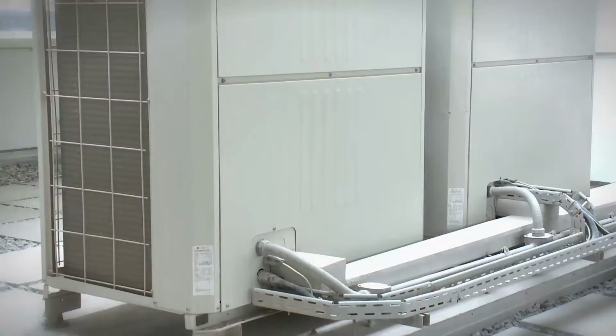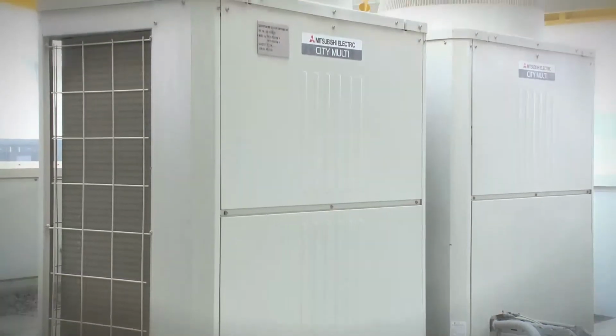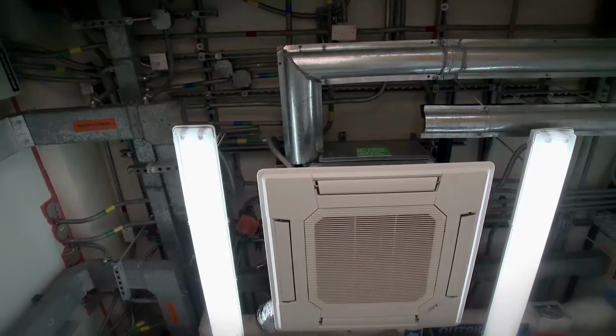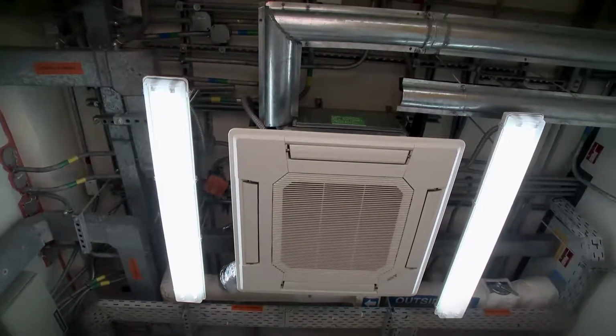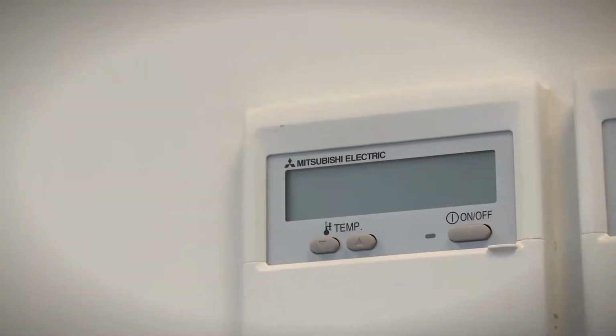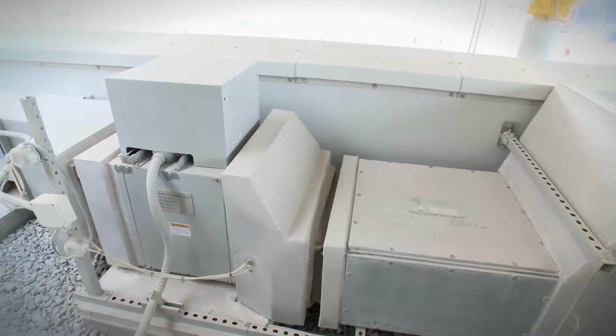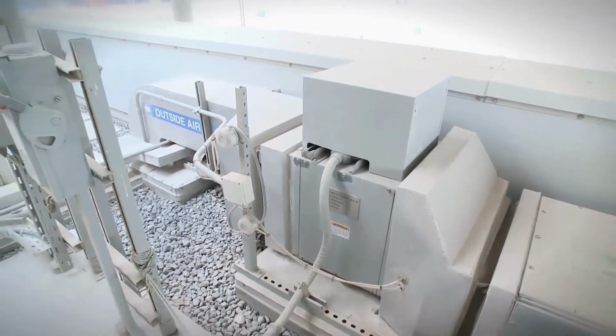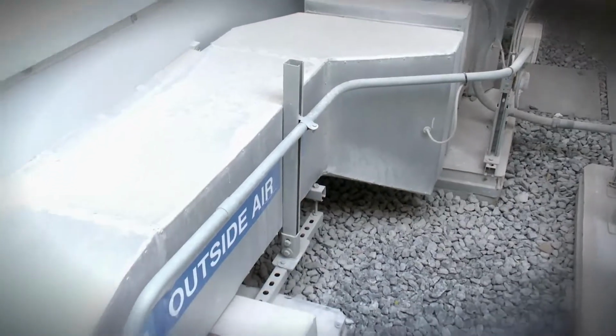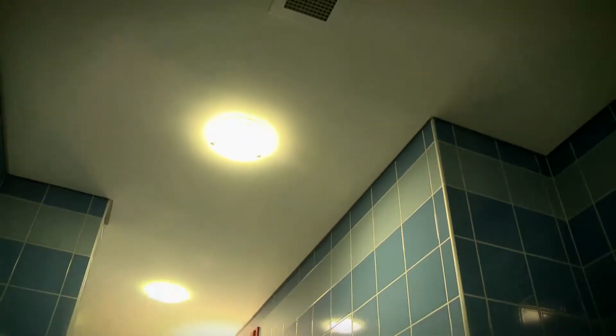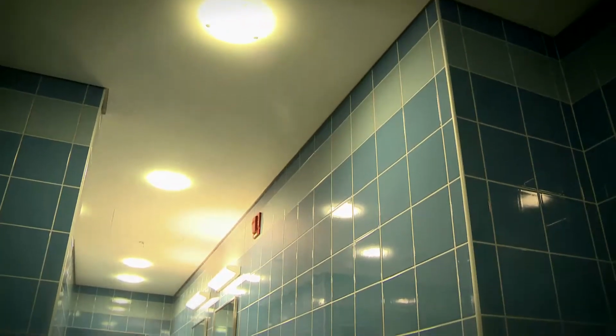The cooling requirement is 24 degrees centigrade, and relative humidity is 50 percent. In order to achieve this cooling requirement, we are using the variable refrigerant volume split units, which will be installed on the roof, and we have the cooling unit inside each room, and each room is controlled by its own thermostat. Whatever temperature you need, you can set it individually in the rooms, and then each unit is supplied with fresh air, so that you will have good quality of air inside the building. Simultaneously we are extracting the air from the kitchen and the toilet area to compensate the air balancing system in the building.